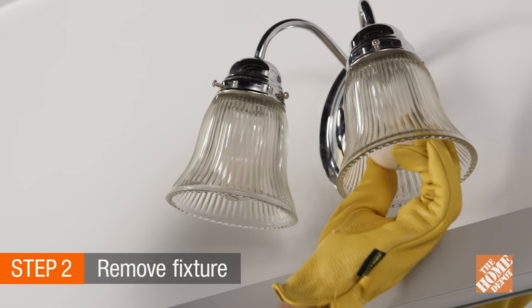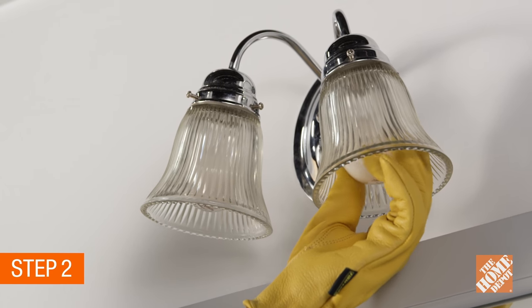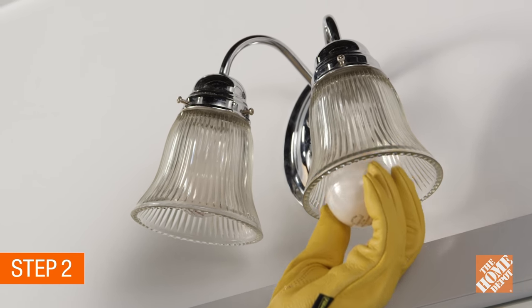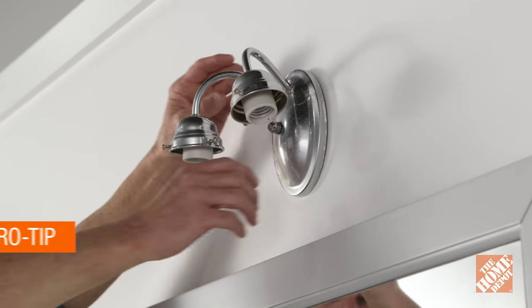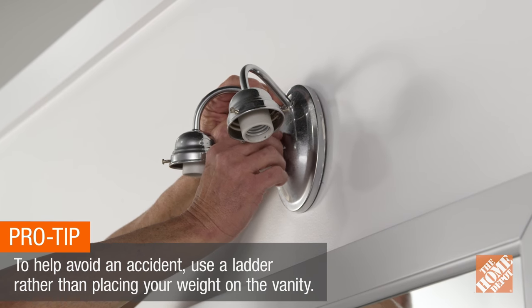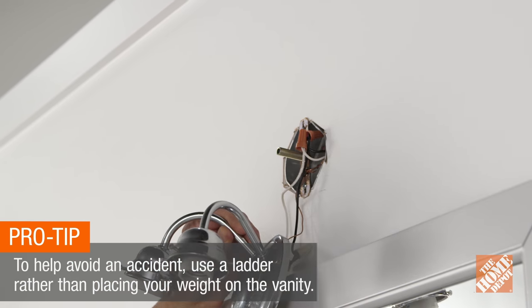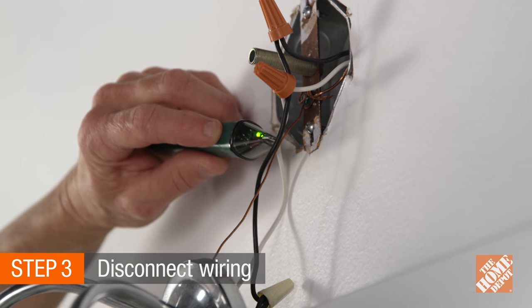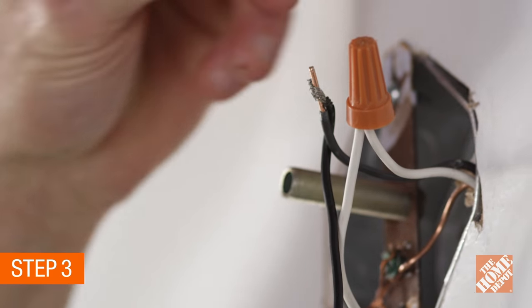Now remove the existing fixture. Take out the bulbs, remembering to wear gloves if the bulbs are hot. Unscrew the retaining screws and take down the shades. Remove the suspending screws or nuts from the outer portion of the fixture to slip off the cover and expose the wiring. Use the volt pen to double check that the power is off, then carefully remove the wire nuts.